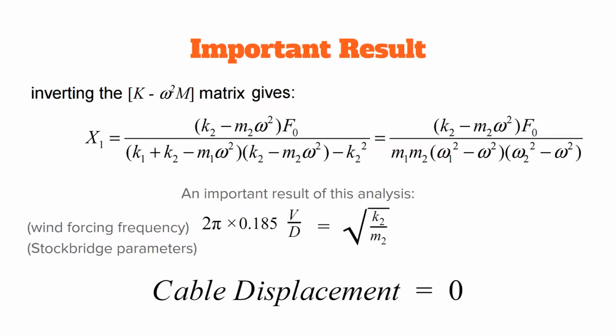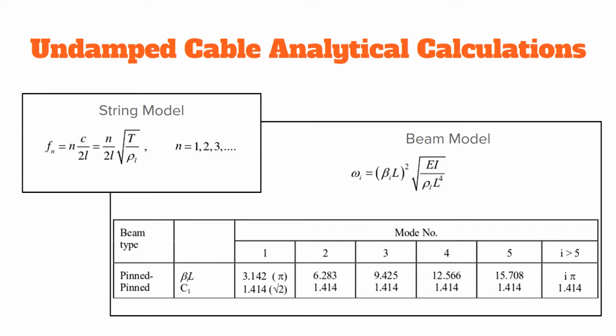The most important result of this analysis is that the amplitude of the cable can equal zero. This would theoretically occur when the forcing frequency matches the uncoupled single degree of freedom natural frequency of the Stockbridge damper. According to this analysis, the Stockbridge damper should be tuned to the forcing frequency on the cable, which is produced by the wind. In order to verify results from the experimental and simulation models, the undamped cable natural frequencies can be calculated using string and beam theories of transverse vibration. The beam solutions are useful for comparison with a Strand7 finite element model, which uses beams.